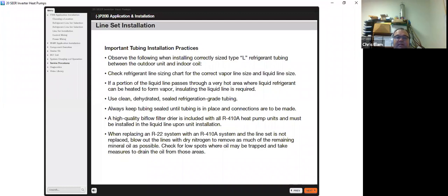Use clean, dehydrated, sealed refrigeration grade tubing. Always keep tubing sealed until tubing is in place and connections are ready to be made. Quality bi-flow dryer is included with all 410A heat pump units and must be installed in the liquid line upon installation.